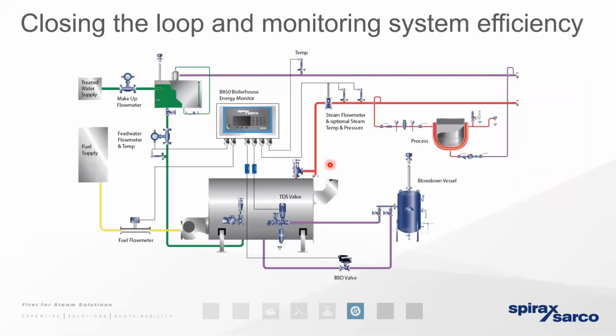So on the subject of meters, another way that we can help to understand the overall efficiency of the wider steam and condensate loop is by fitting an energy console in the boiler house. And that console can take an input from any number of meters around the energy center. For example, if we're metering the water coming into the building, the fuel coming into the boiler, the water leaving the feed tank and going into the boiler, and the steam that's leaving the boiler, well, we can take an input from all of those meters.